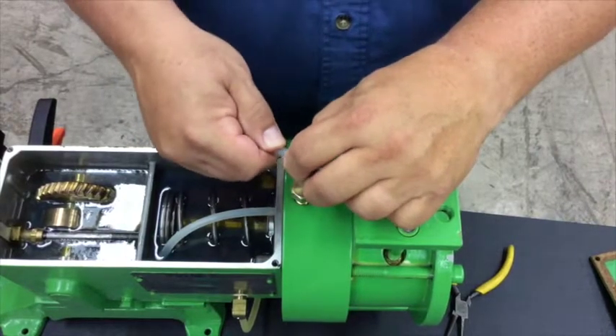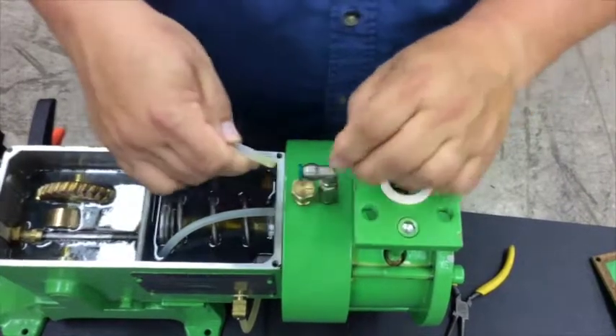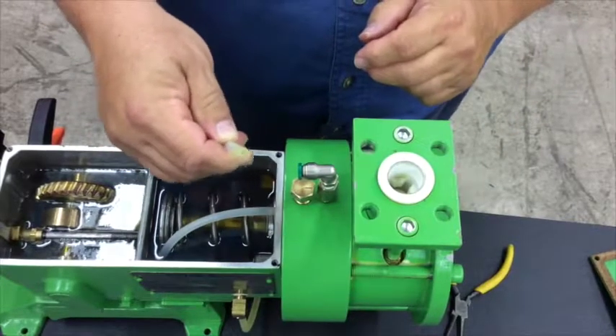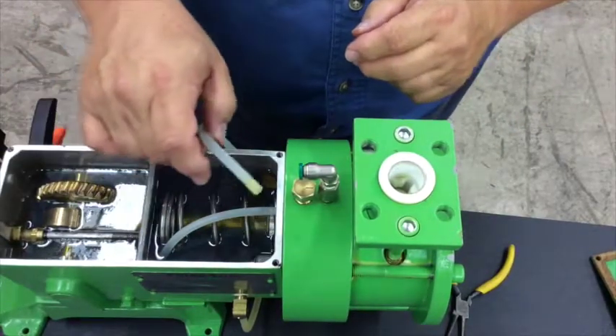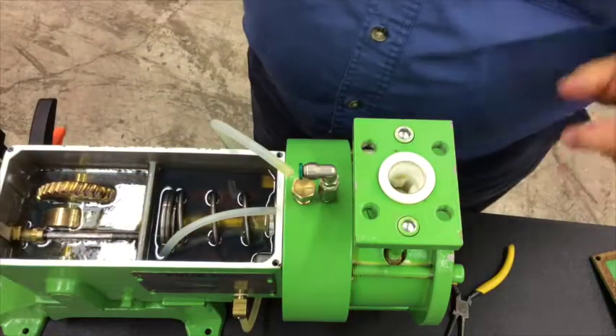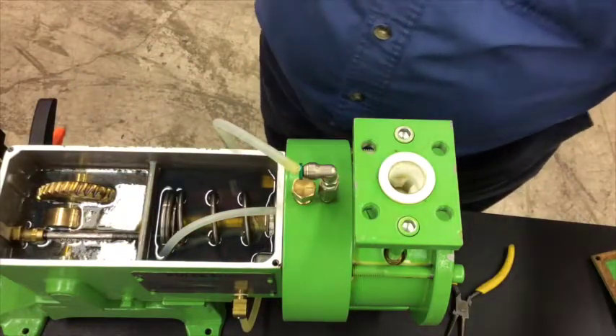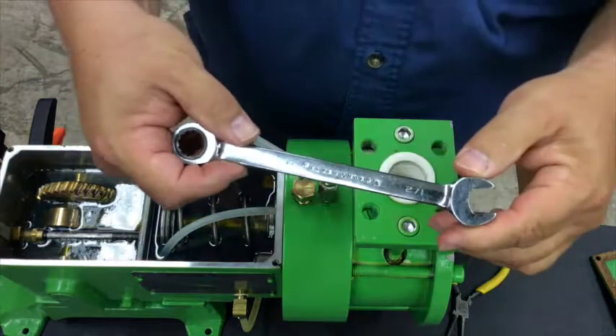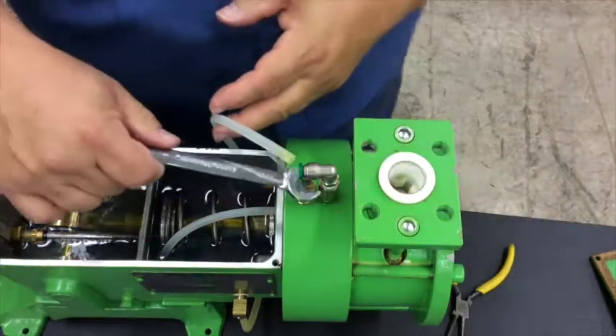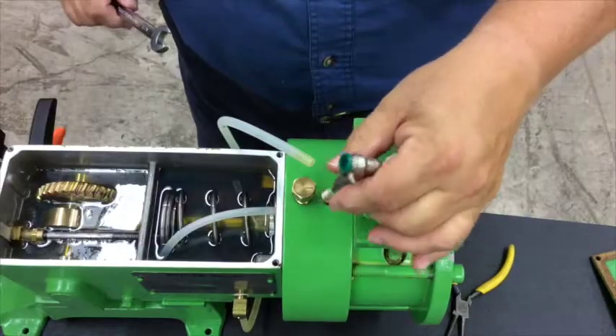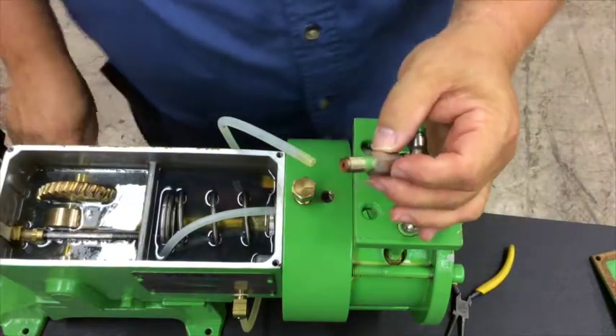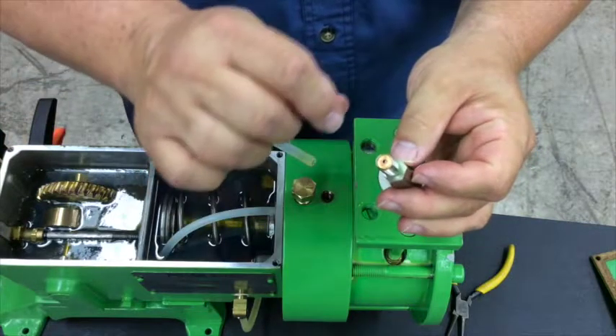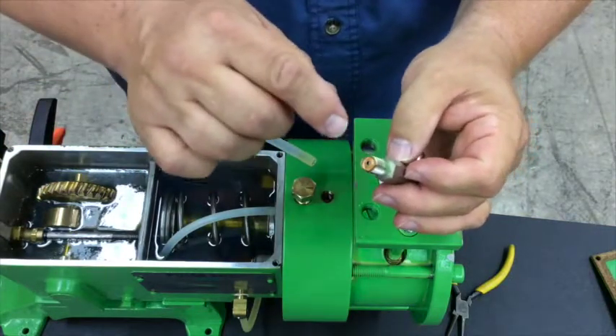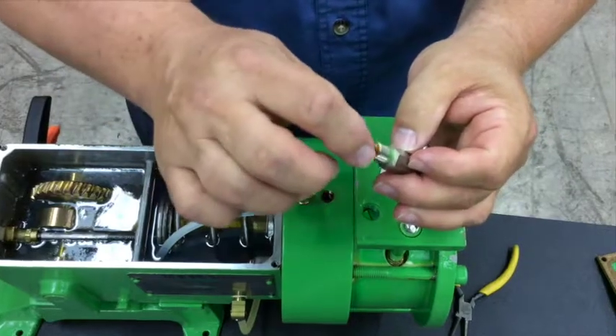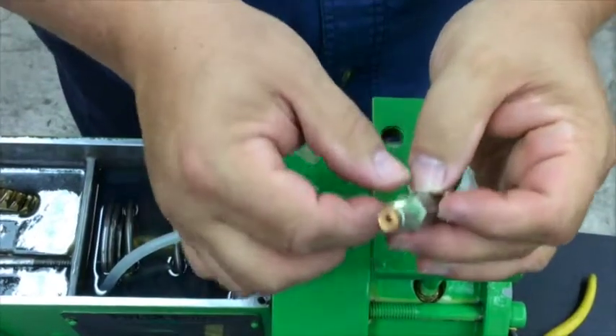Okay. There it goes. So I've removed the tube from the air bleed valve. I'm going to just set it there, and I'm going to use my 1/2-inch combination wrench to remove the air bleed valve. So I've got the air bleed valve, and make note that there is this copper crush washer which provides the seal between the air bleed valve and the port. So I'm just going to make sure I don't lose that. All right, you can see the washer. Let me set that aside.